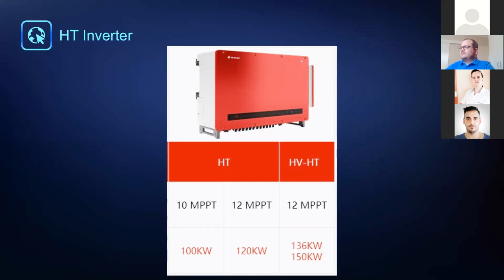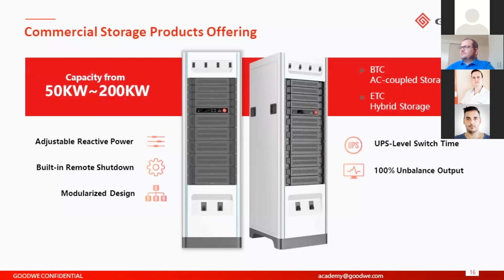And then lastly, our BTC and our ETC range of storage commercial products. Both of them will have adjustable reactive power. They'll have built-in remote shutdown. It's a modularized design, with 50 kilowatt modules, up to 4 50 kilowatt modules to have a 200 kilowatt product. And then UPS level switch time, and it will also be able to manage 100% unbalanced loads on the output of the inverter.